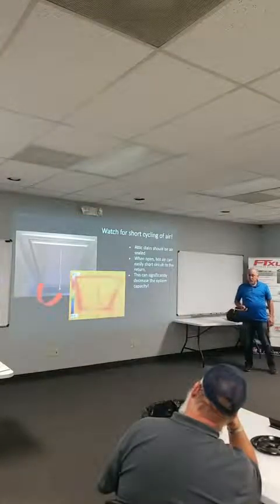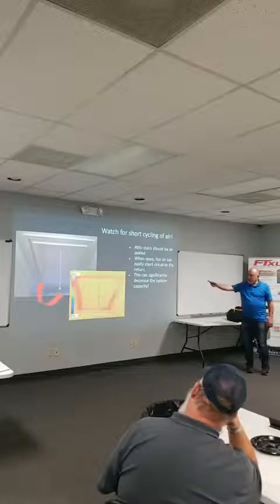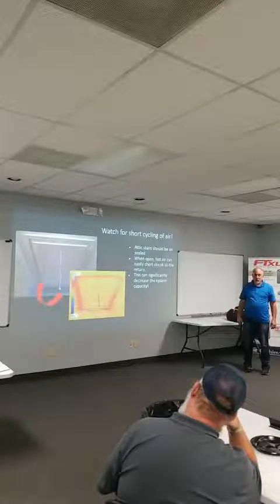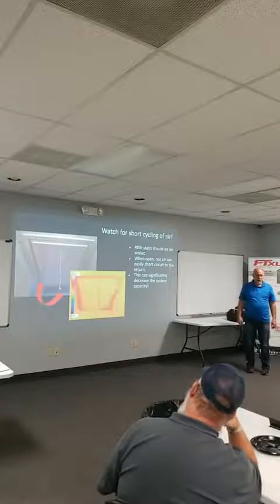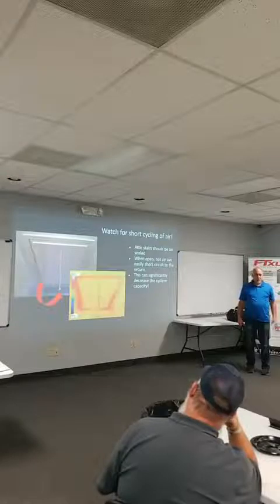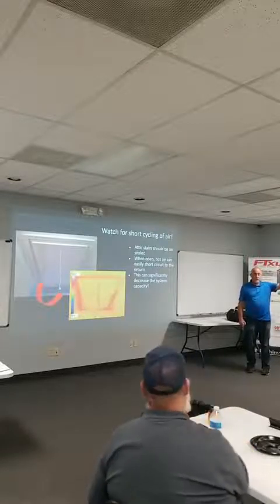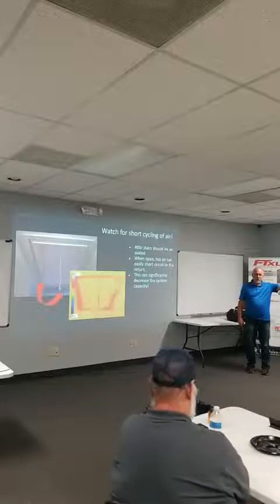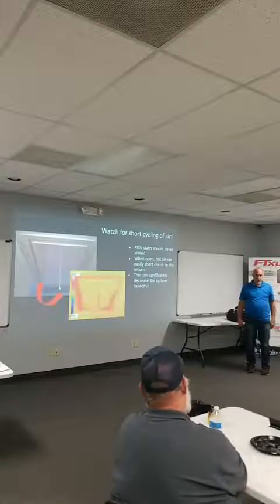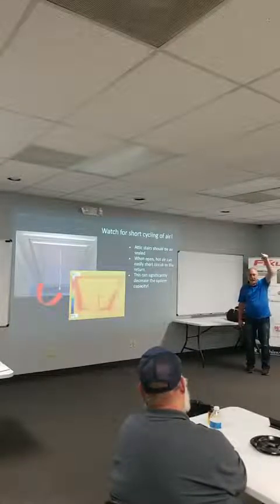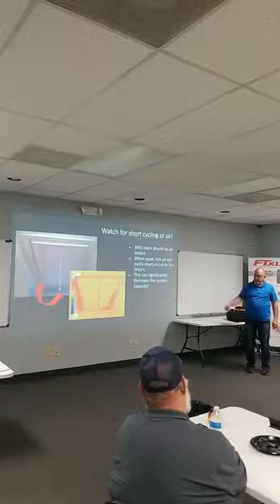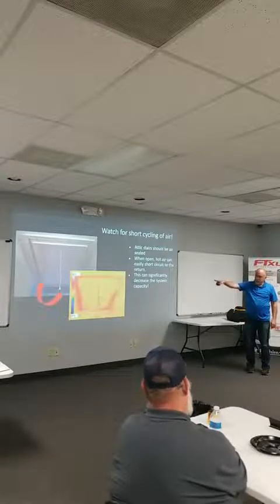Another big problem, especially on the residential side, but this can happen on the commercial side as well, is we're not paying attention to what's next to our returns. Now, I've done this before. I've gone up to pop my head up to a ceiling, and you know it's hot as hell up in the ceiling because it's unconditioned space right above you. And all of a sudden, you're doing something up in the ceiling, you're not realizing that you're affecting the equipment operation because you got hot air coming right out of that ceiling and going right in that return. This is exactly what's happening right here: we're depressurizing the zone.